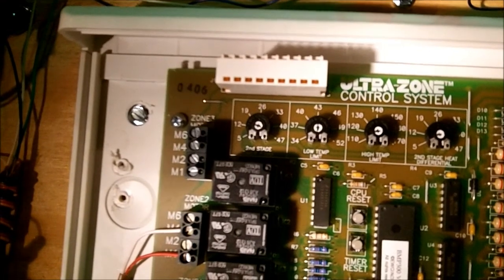So let's talk about the dials on the board. So right now the blower is running, so it's going to take a while to cool that supply air sensor down. All right, so the first dial we have is our second stage timer, or our outdoor sensor. Right now I have the outdoor sensor set for around 17 degrees, or if there wasn't an outdoor sensor, it would be 17 minutes.